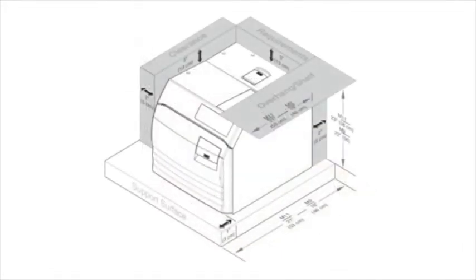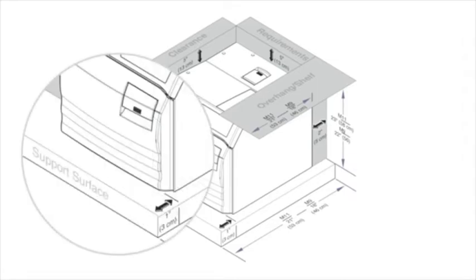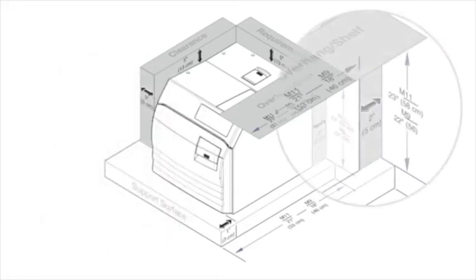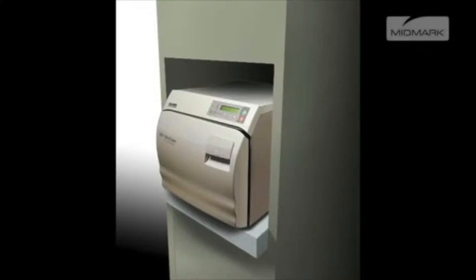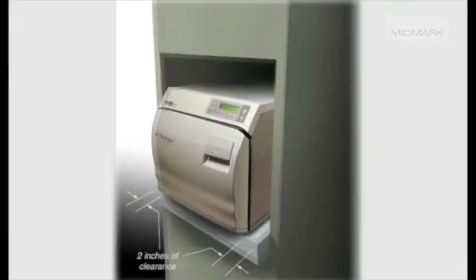This illustration can be found in the Installation and Operation Manual. It provides critical information for installing the autoclave, including type of support surface, recommended location, and minimum clearances around the unit. These recommendations must be followed to ensure optimum performance of your autoclave. Be sure your unit has the following clearances around it for proper air circulation.